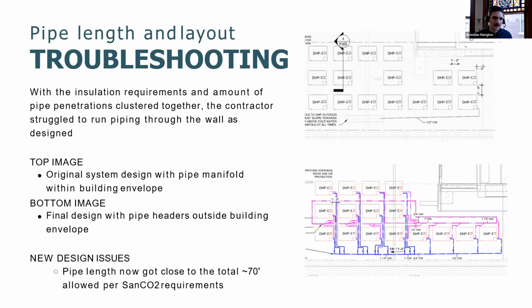This was dealt with just by working with the manufacturer, upsizing some piping. Since the heat pumps have their own integral pump, we really need to be cognizant of the total pump head. And we just increased the pipe sizing, worked with the manufacturer, and we're able to get this to work. But that is something that you need to consider when designing these systems.